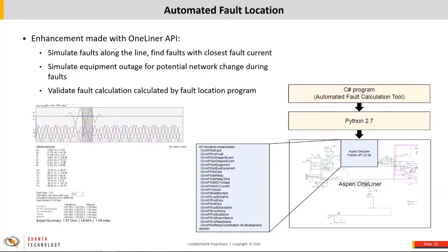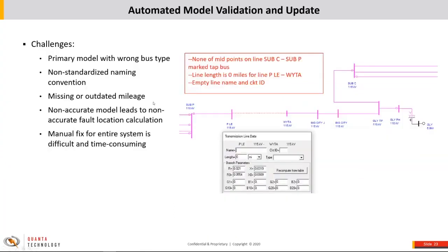This screenshot shows the proof of concept for the fault location program. It takes the recorded fault records, draws the curves on screen, gives all measurements, detects the fault type, and comes up with a fault impedance calculation and mileage. If the mileage exists in one-liner, it maps it. The program calls the API functions through Python.